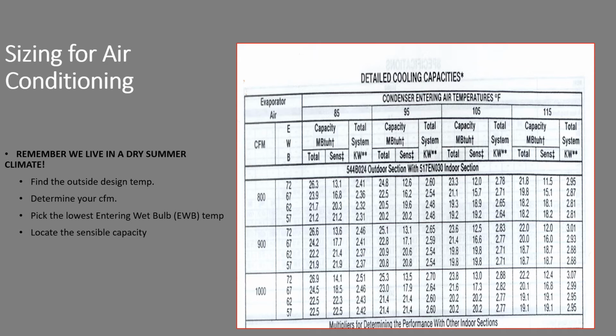So again, these charts are only valid if you have perfect airflow and perfect charge. You pick the lowest entering wet bulb. 62 or 57 degrees is safe. Remember, it's going to be hot. The air conditioner is going to be running for a long time, and the air will get dried out the longer that air conditioner runs.